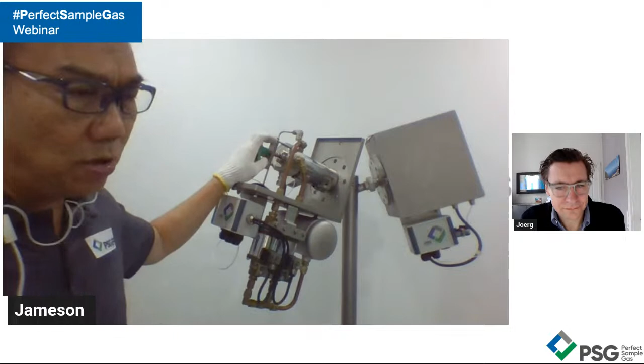Now, look at the air tank here. It is very important that the distance between the air tank and the sample probe must not, I repeat, must not be longer than 0.5 meter. Keep it as short as possible. The reason is, as I mentioned earlier, it's the pressure, not how much flow has been wasted. It's how much pressure, all right? So they have a very, very big solenoid valve, right? In our case, we have a 12 millimeter tubing, incorporated with a specially selected ball valve which also has a 12 millimeter bore to prevent any pressure loss. Once the ball valve swings over, the high pressure from the tank rushes out and is injected into the chamber. Okay, first the filter, followed by the chamber, to remove the amount of particles.